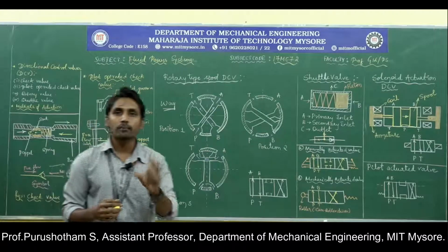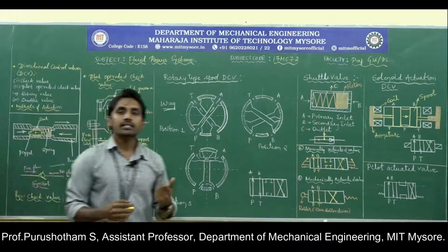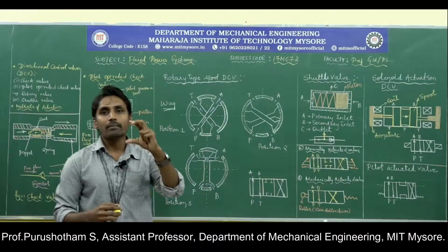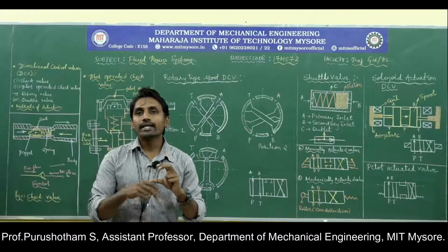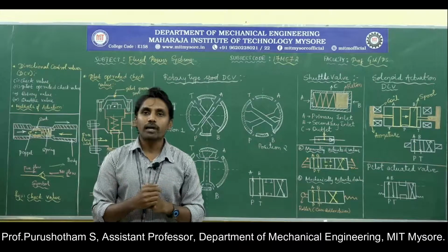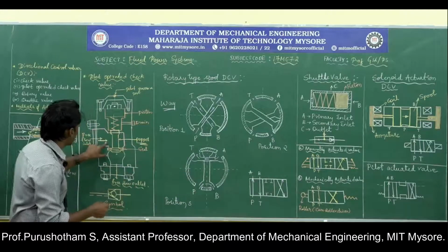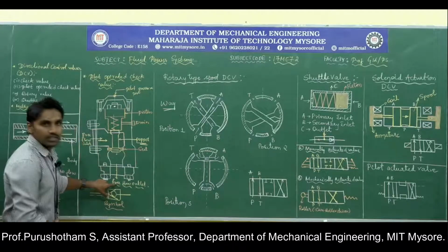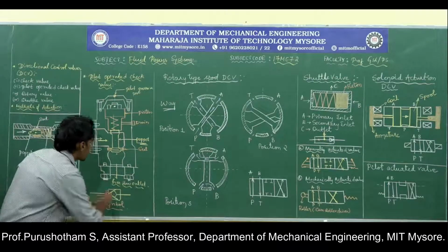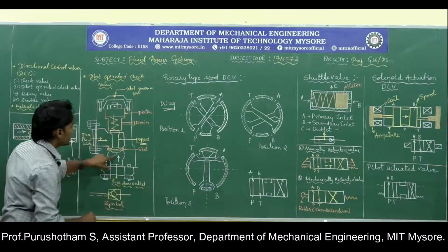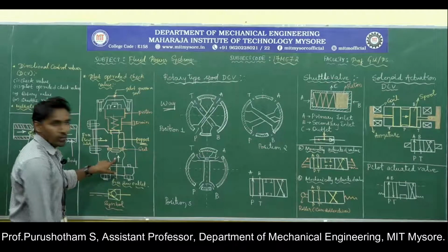That means if you want to hold the pressure for some time, then we go for pilot operated check valves. For example, in some presses, when the ram is actuated against the mold, we need to give some time to get the final product, to get the desired shape. In that time, the fluid flows to actuate the ram and is held for some time, because the fluid pressure entering from this end locks the poppet against the seat. So there is no flow from here.